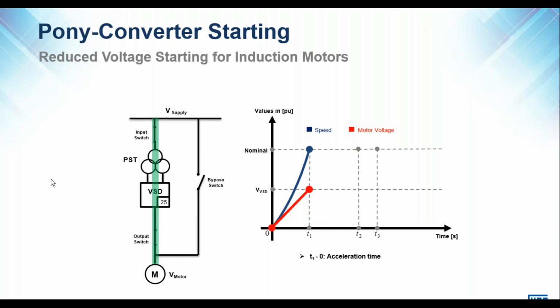Again, provided this is a light starting duty application that does not get to its full load condition at the end of the acceleration curve. In this case, we are able to start the motor. We can see that we ramp up the speed to full speed. However, the voltage output of the VSD is at some percentage below the nominal voltage of the motor itself. After reaching full speed condition at reduced voltage, we can bypass the VSD.